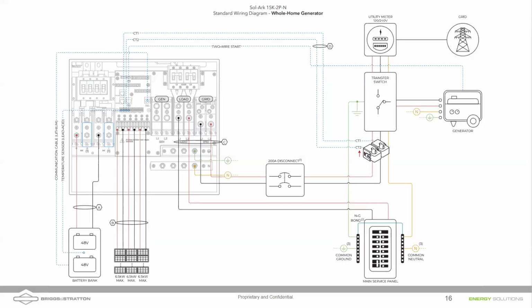On the generator point, I've talked with off-grid customers, and their concern during system operation is when they hear the generator running, they feel anxious because they know they're on a timer. Whereas when they're running with the battery and solar, they realize they're in a healthy range. So that's where taking care to power the battery with the site power rather than an internal battery, which is a feature you guys have, not needing to exercise the generator to charge what would otherwise be an internal battery, and optimizing the runtime really comes into it.